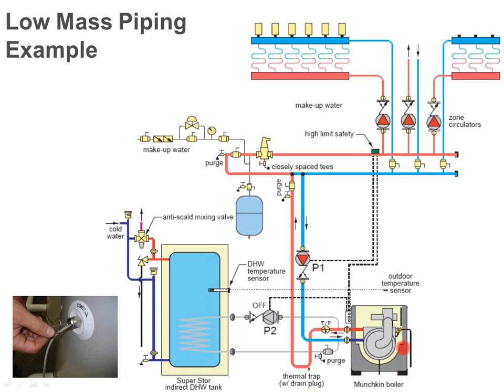And what happens in this application, and we do not add BTUs for the domestic hot water, we prioritize it. So when that DHW sensor calls for heat and says, hey, that water's too cold, it goes to the boiler and says, okay, boiler, I need to make domestic hot water. Forget your outdoor reset curve. I want 180 degree water now. I want you to turn on pump 2, at P2 there, shove all that boiler hot water into that coil in that tank, shut off P1, I don't care about the heating right now, and heat up that water in that tank as fast as possible.